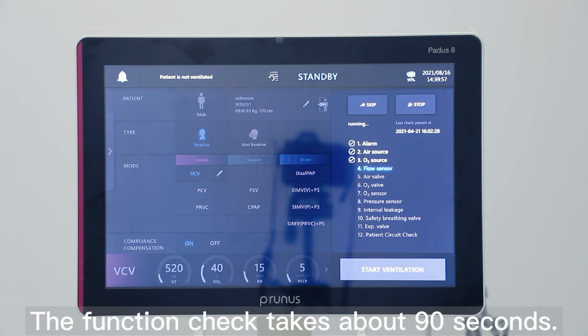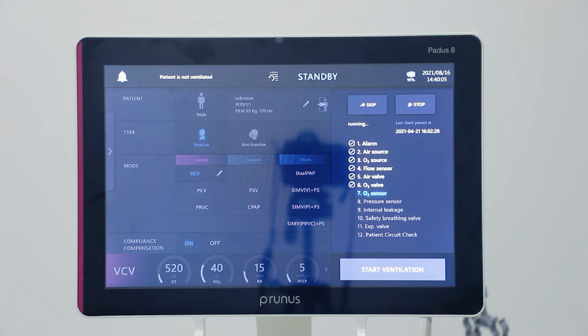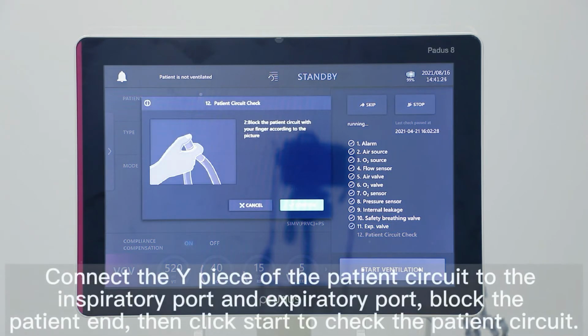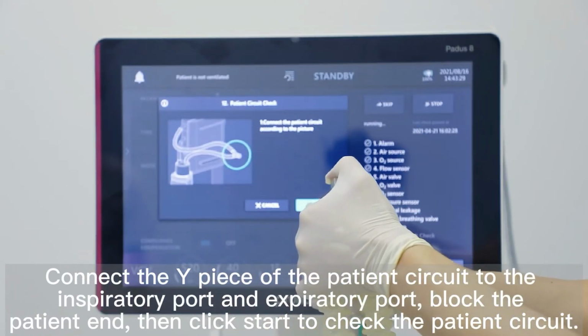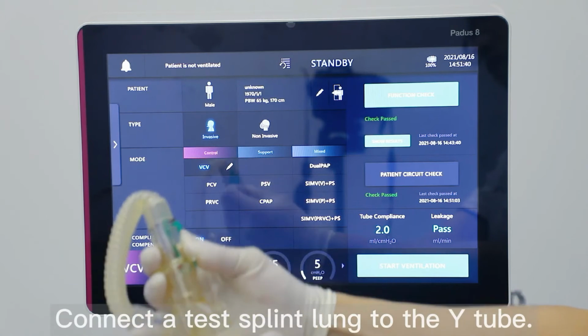The function check takes about 90 seconds. Connect the Y piece of the patient circuit to the inspiratory port and expiratory port. Block the patient end, then click Start to check the patient's circuit. Connect a test splint lung to the Y tube.